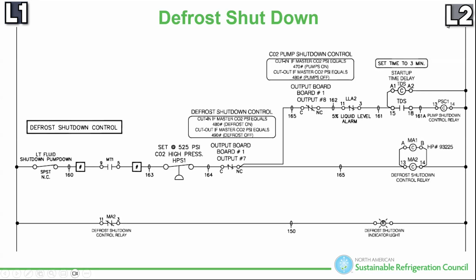I'm going to take my black lead and come up here to the control breaker, L2. I'll loosen it just a touch and slide my black lead under L2. This way I don't have to touch it or move it. One of the things I want to do is use one hand as much as I can, because if I'm touching both hands on the electrical panel and there's a short, remember electricity's trying to go to source, so the quickest way to ground would be through me.